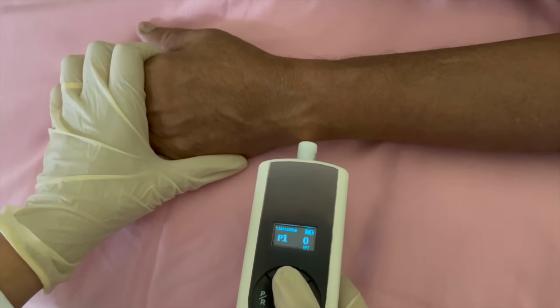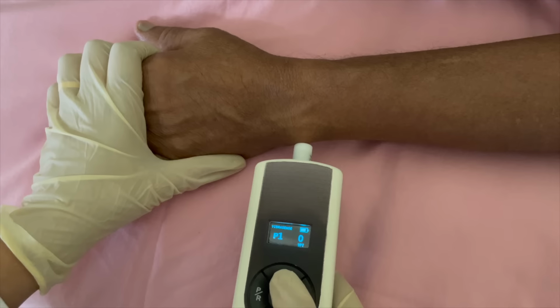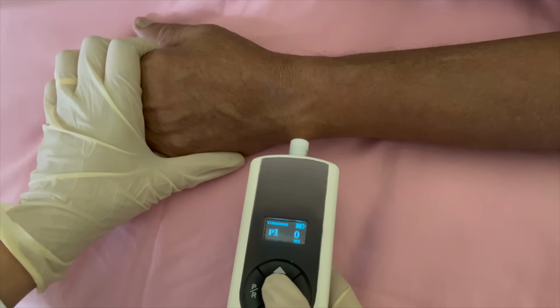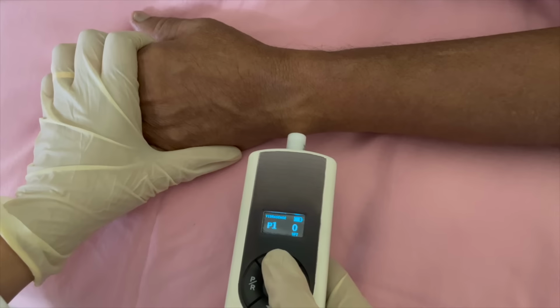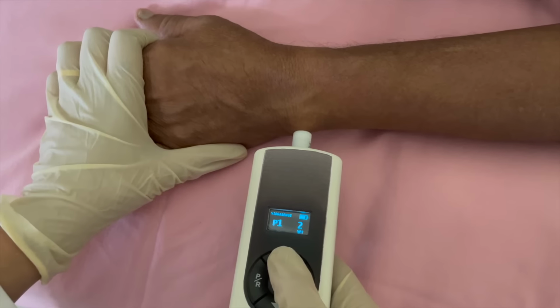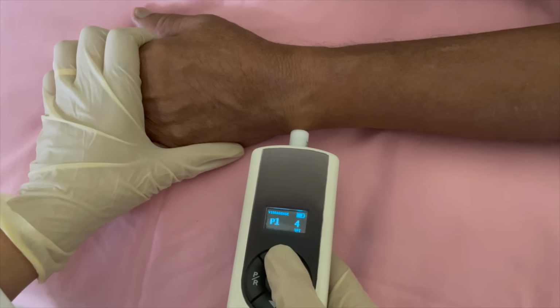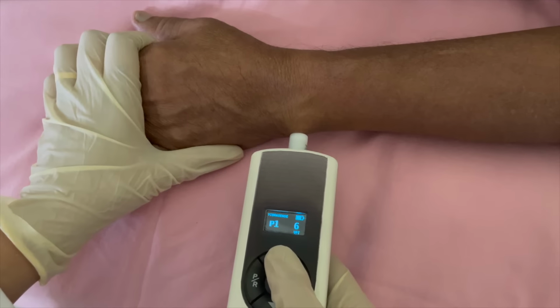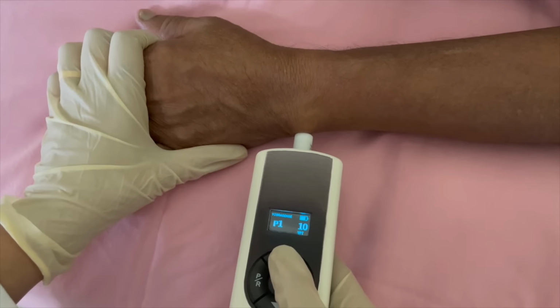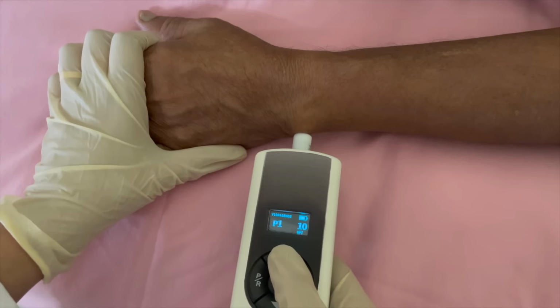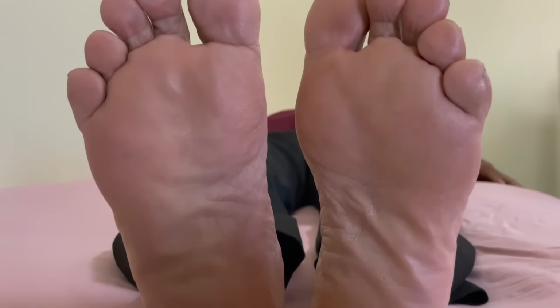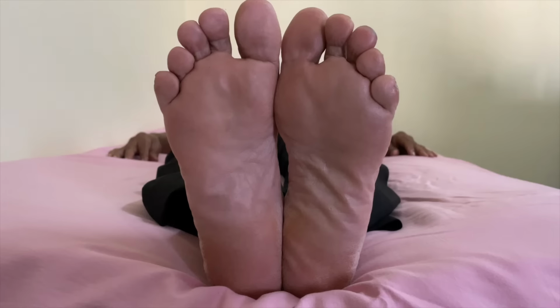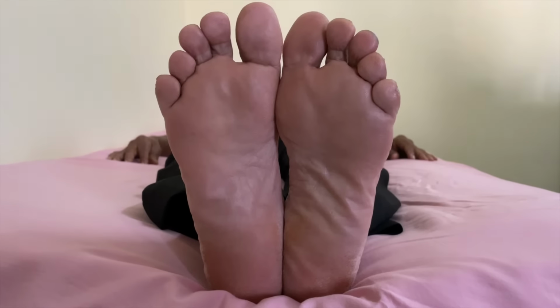Before testing the feet, train the subject to sense vibration stimuli. Place the probe on the dorsum of the subject's hand and use the up arrow to increase the vibration stimulus until the patient feels a buzzing sensation. Tell them you are going to give a similar stimulus in the foot. Instruct the subject to affirm by saying yes or by thumbs up sign as soon as they feel the buzzing sensation on the foot being tested.